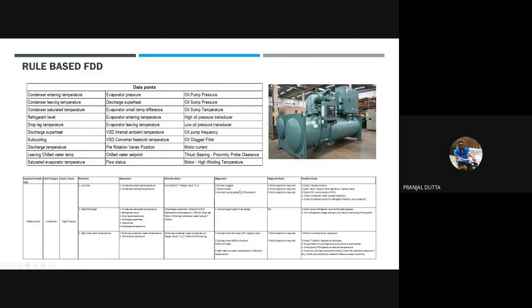Next, how diagnostics will be done for this particular error. The diagnostics could be strainer clogs, valve closed, or incorrect pump speed. We run diagnostic rules, and these rules are written in this application. Based on these rules, the errors appear in the system and go to the maintenance team, like low pressure or high pressure existing in this particular chiller, and these are the reasons. It also gives you the checkpoints for what needs to be checked. Let's say for low flow: clean and repair strainers, open the valves. So it covers the entire cycle of the system.